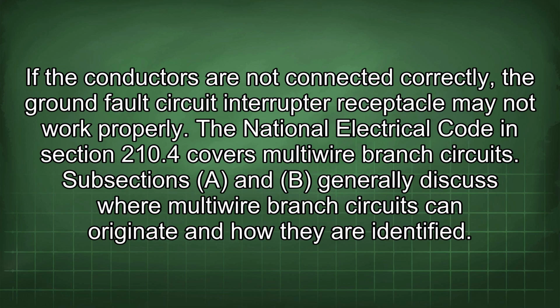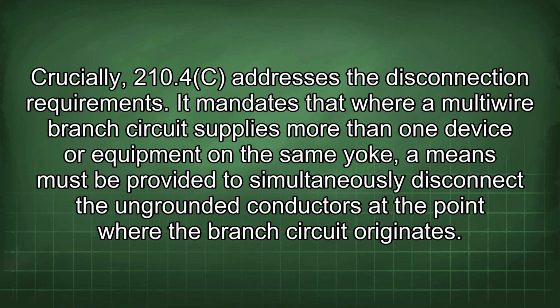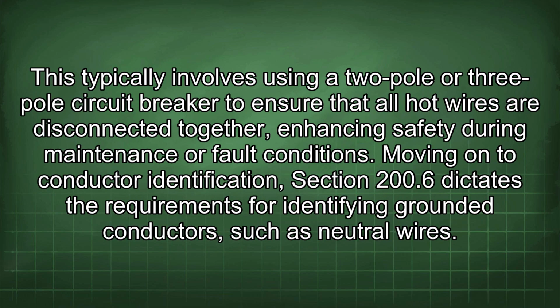The National Electrical Code in Section 210.4 covers multi-wire branch circuits. Subsections A and B generally discuss where multi-wire branch circuits can originate and how they are identified. Crucially, 210.4(C) addresses the disconnection requirements. It mandates that where a multi-wire branch circuit supplies more than one device or equipment on the same yoke, a means must be provided to simultaneously disconnect the ungrounded conductors at the point where the branch circuit originates. This typically involves using a 2-pole or 3-pole circuit breaker to ensure that all hot wires are disconnected together, enhancing safety during maintenance or fault conditions.